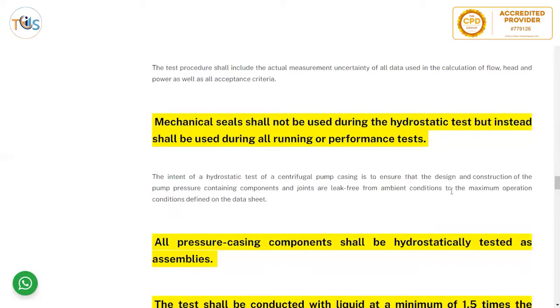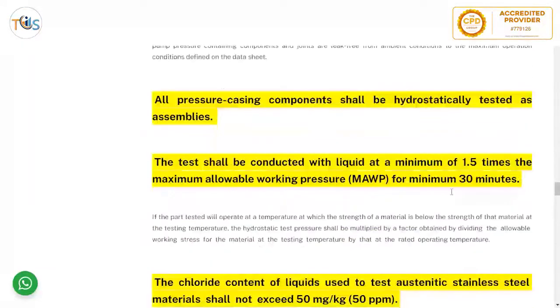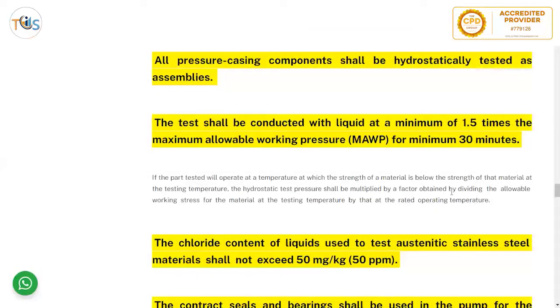The intent of the hydrostatic test of a centrifugal pump is to ensure the design and construction of pressure-containing components and joints are leak-free from ambient condition to the maximum operating condition defined on the data sheet. All pressure casing components shall be hydrostatically tested as assemblies. The test shall be conducted with liquid at a minimum of 1.5 times the maximum allowable working pressure held for 30 minutes.